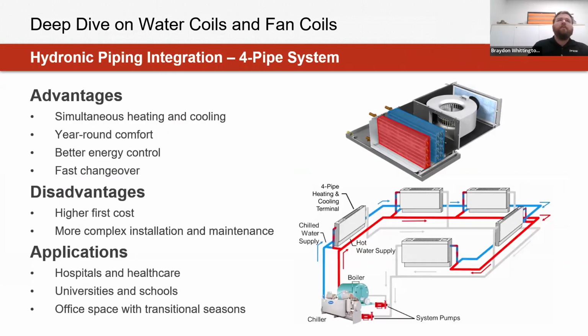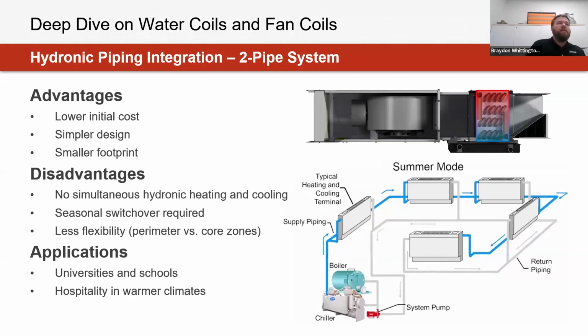Some advantages I would say for 4-pipe systems are simultaneous heating and cooling, which can be beneficial for some dehumidification within the space, and allowing for that fast changeover. But a lot of the time, where we might not see these used is the fact that it comes at a higher cost. And in terms of adoption, it can get more complex from an installation perspective. 2-pipe systems are beneficial for their smaller footprint required for installation, and we also see a lower initial cost within those systems.